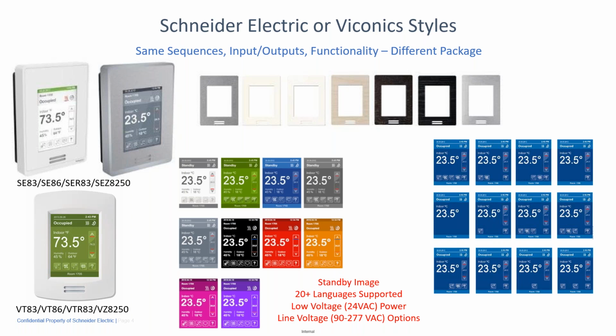That's always a white case and fascia, one piece, no logo, and it fits any environment, right? You're capable with the controller, through the configuration screens, to pick any one of the color screens you see there. So there's white, green, blue, gray, dark gray, black, red, orange, all different colors, purple. You can change those just from the face of the controller. I often questioned why they have so many different colors. Well, one reason is for aesthetic purposes, but some people have the face of the screen change based upon the mode. If I'm in heating mode, it's red. If I'm in cooling mode, it's blue, to fit that particular kind of application.